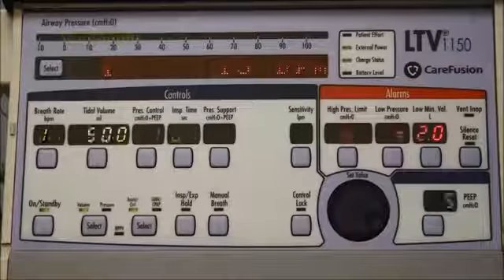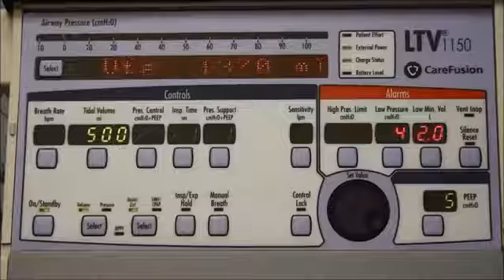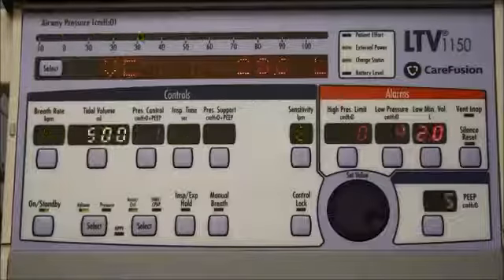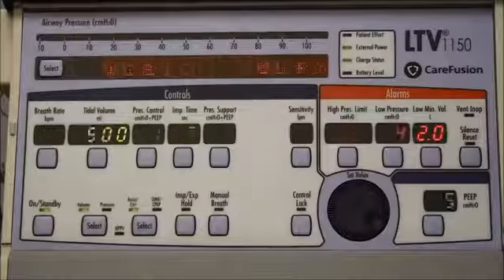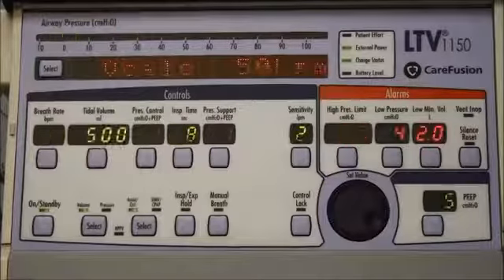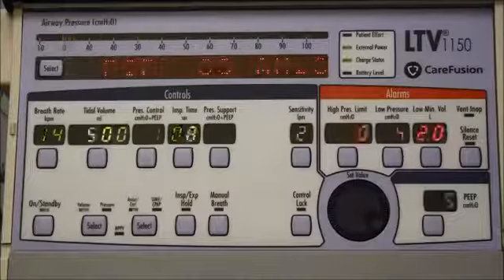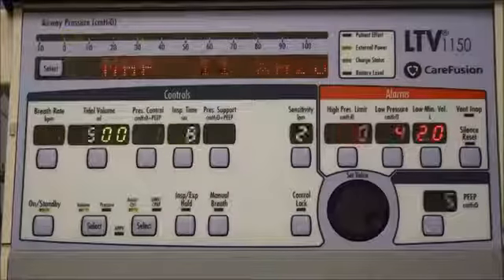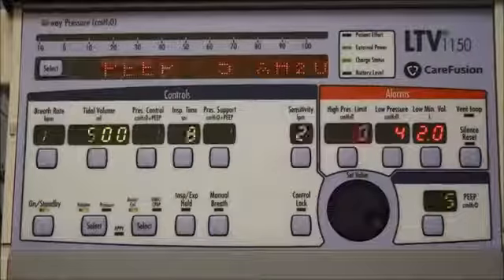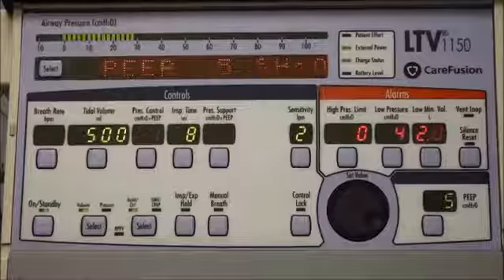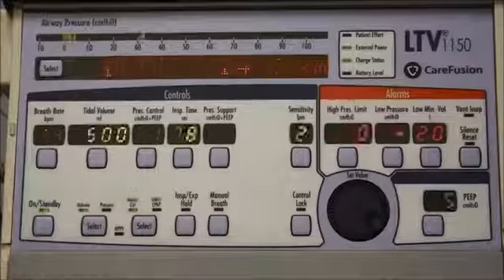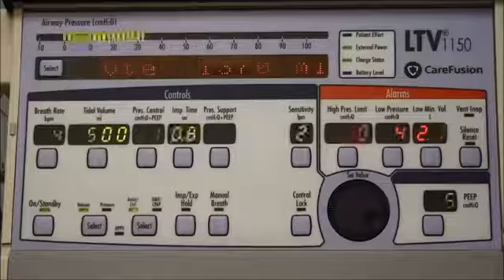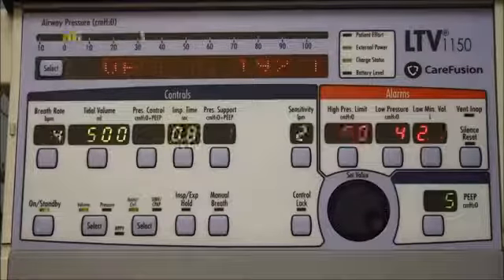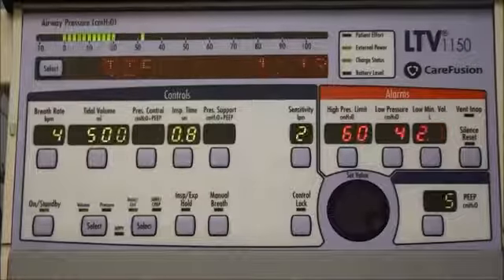Now I'm going to talk about the alarms that you can see on the front of the ventilator. There's a number of different alarms that are set internally on a different menu, but there's 3 alarms that you can set on the front of the ventilator: the high pressure, the low pressure, and the low minute volume. Now these are typically not ordered by a physician. They are set according to what particular patient needs it to be set at, according to what his pressures and his volumes are at.